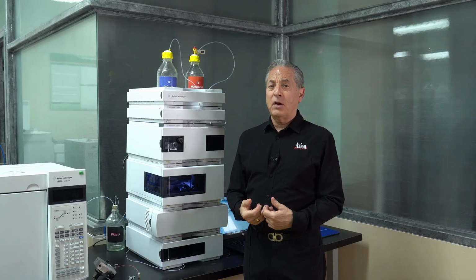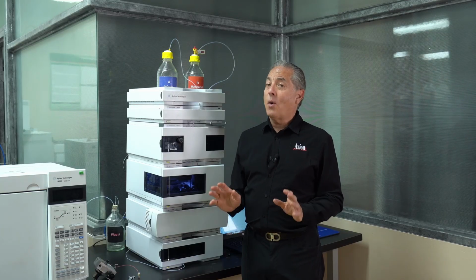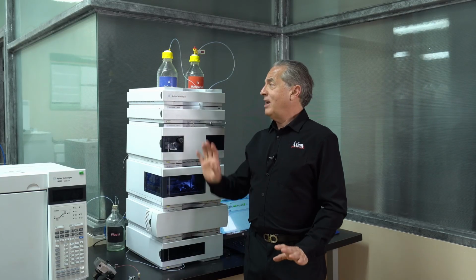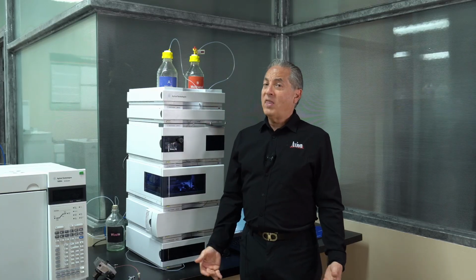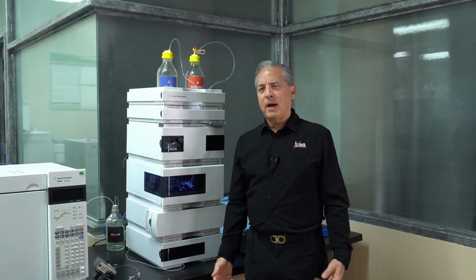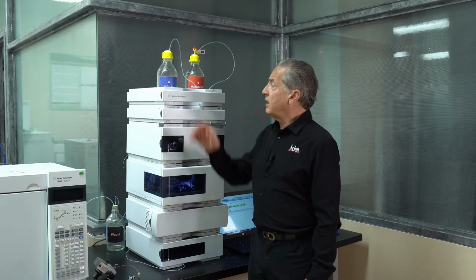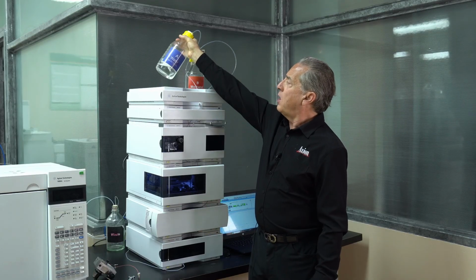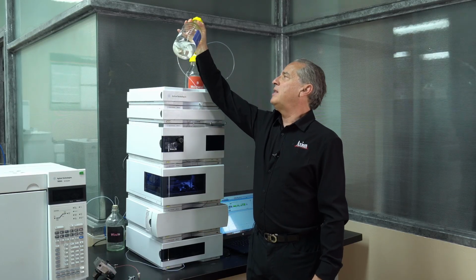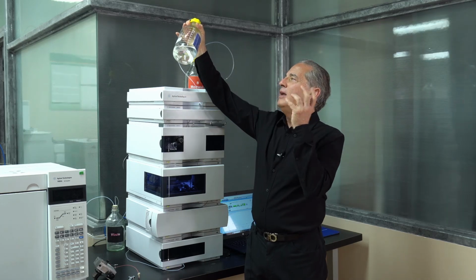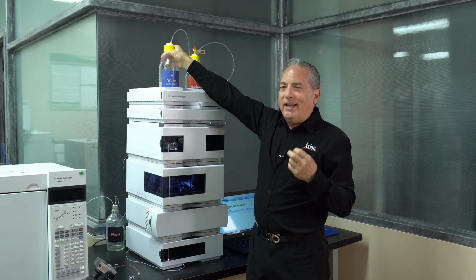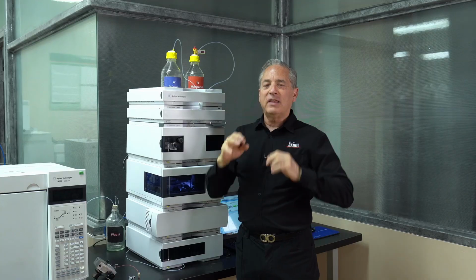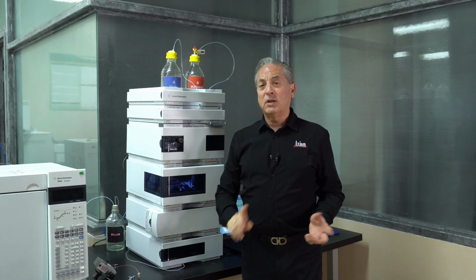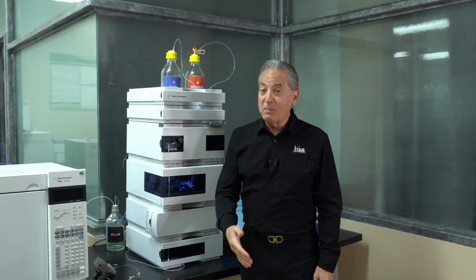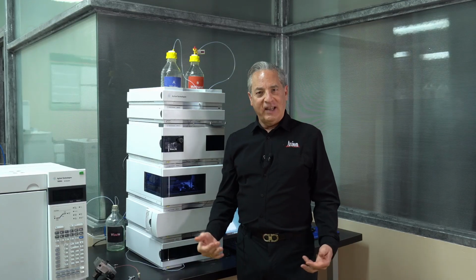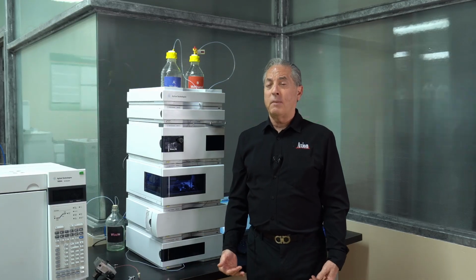I use 5% methanol. I'm no microbiologist, but I could go a month, guaranteed a month, without getting any kind of growth in the water bottle. Without that, you would have a problem within a couple of days. Certainly within a week, you would see floaty things. So whenever I pick up the water bottle, I always swirl it and then I hold it up to the light. And what I'm looking for is little floaties. Any tiny little things that look like strings or anything like that. If you see any floaties at all, you should dump that bottle, rinse it out, rinse it with some methanol, sterilize it, and then let's go back to the beginning and make the water bottle clean.